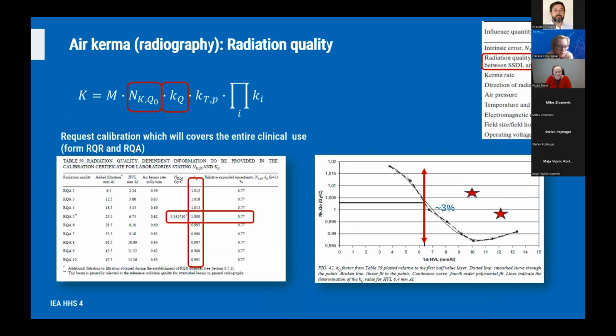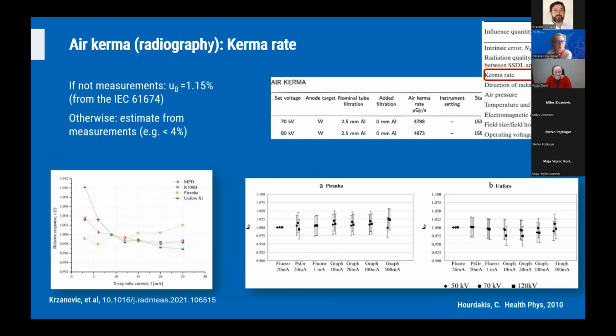And as you can see in this example, the relative expanded uncertainty of calibration is 0.7 or 0.8% for the range of standard radiation qualities. However, the calibration factors are quite different. So if we apply separately all these calibration factors for different radiation qualities, we would be able to reduce the uncertainty of measurements by 3% and keep only the component attributed to the uncertainty of the calibration factors. Otherwise, the uncertainty would be 4 or 5%.